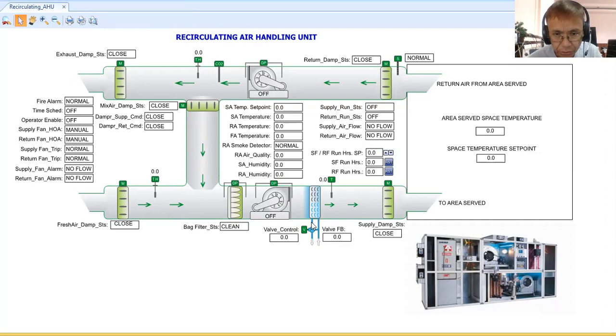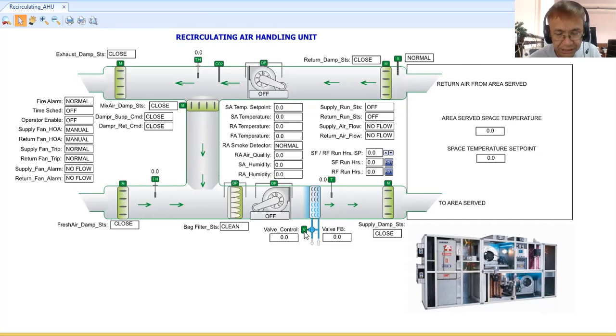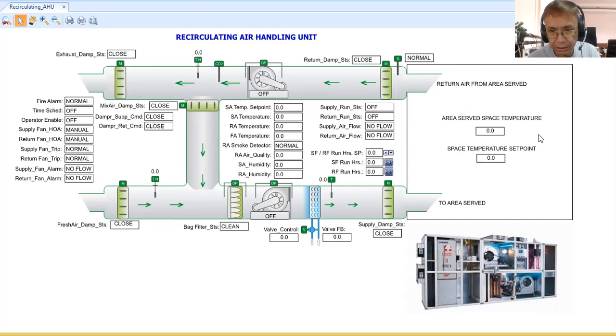There is a valve actuator that controls the chilled water entering the cooling coil. The control logic implements PID control — proportional plus integral plus derivative — to control the valve based on the setpoint and the measured variable.